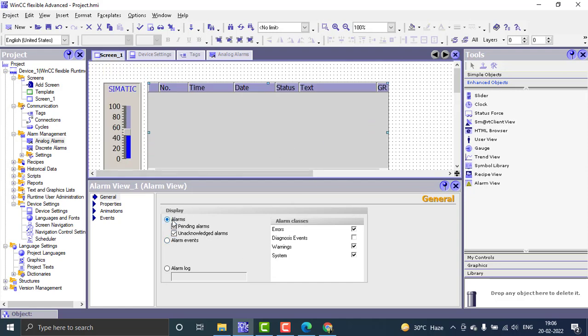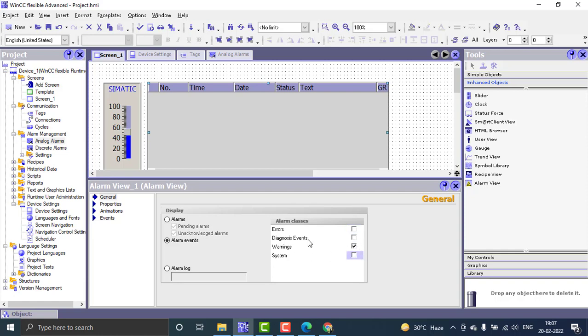In the properties of the alarm display, you can use 'normal alarm' — which shows only current alarms — or 'alarm events', which shows all alarms that occurred during the runtime. You can also assign which alarm classes to display. I only want to display warnings, so I filter it to warnings only.